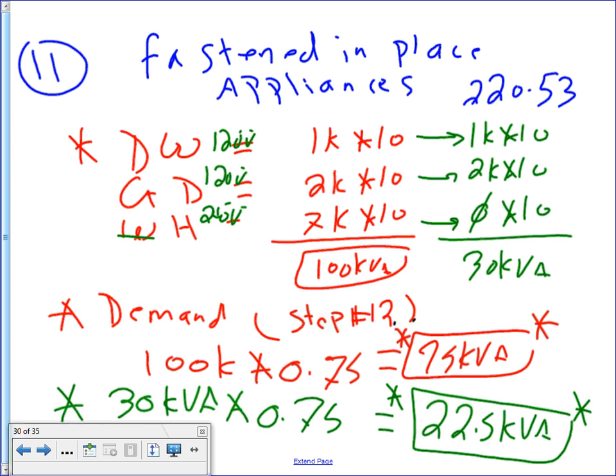Do you see how this step's slightly different, Adam? And I think you were working on it yesterday. When you pull these, anything 240, you have to do some math here. You can't just take that number because some of them don't count. Can you just see that this does not count for the neutral? Why? Because it's 240. It's not going to be seen by neutral. Anything that's 240, not seen by the neutral. Step number 11. Step number 12. Am I going too fast, too slow? Yes, no? Okay. Step number 12, guys.